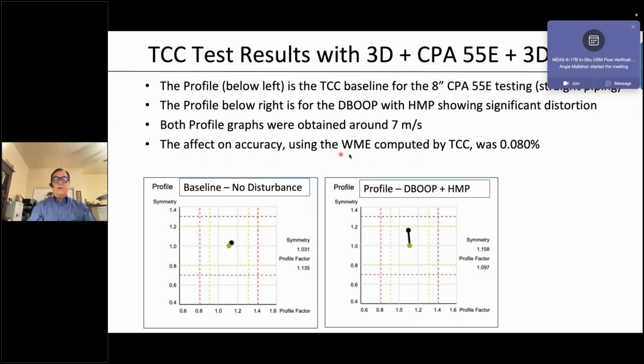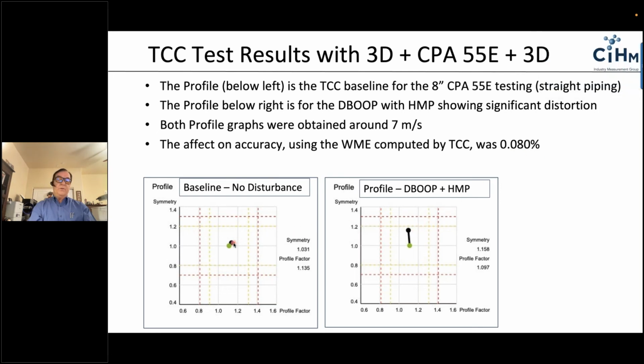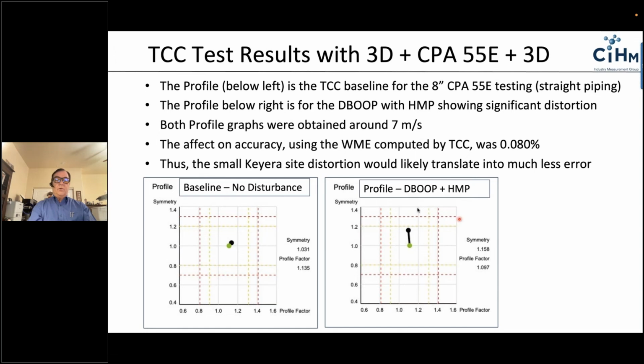The effect on accuracy was about 0.08%. In other words, TCC calculates the flow weighted mean error on this based on the flow data, and it showed about 0.08 for this profile versus this profile. So I think we can assume that the distorted profile we see at the site would likely create quite a bit less error. And again, we're talking under 0.1%, which is less than 1/3 of the maximum permissible error by TransCanada.